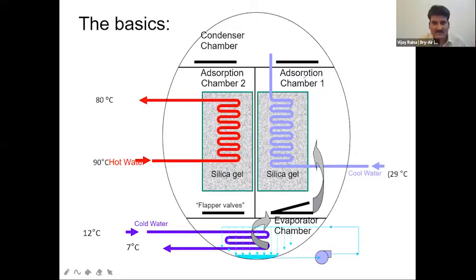So when adsorption is happening in chamber 1, in chamber 2 we give hot water to regenerate it and make it ready for another 5 minutes, because this is a cyclic process. We cannot use only a single bed to transfer the refrigerant water from the evaporator to the condenser and back into the evaporator. So we use 2 chambers separately, a cold chamber and a hot chamber. In the hot chamber the pressure is definitely high, so this flapper is closed. In the cold chamber the pressure is low. This is a hot chamber, evaporator. This flapper is on.